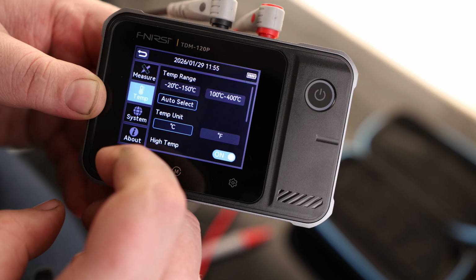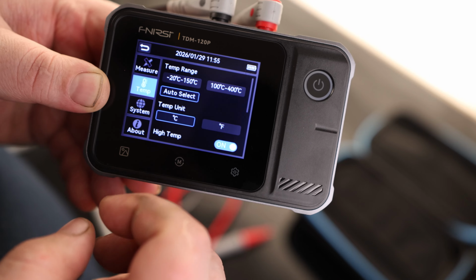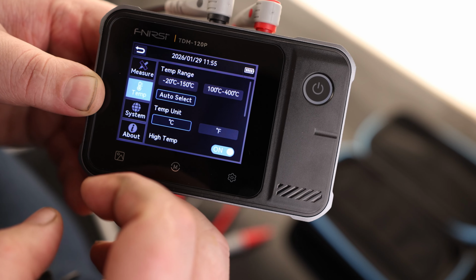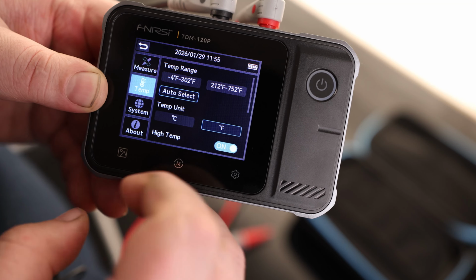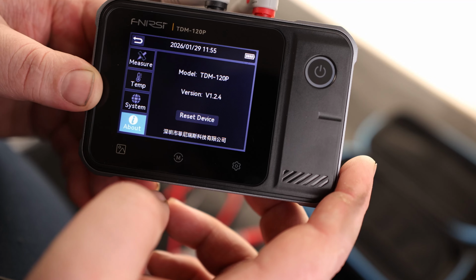We can set our emissivity, we can set our temperature range, so if we need to measure something very hot, we can set that to 400. It's currently in Celsius, we can set that to Fahrenheit. In system settings, we have our auto off and about.